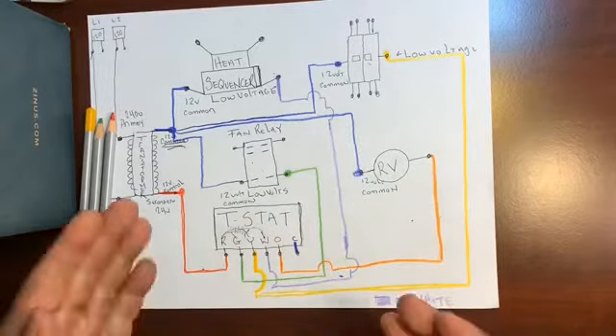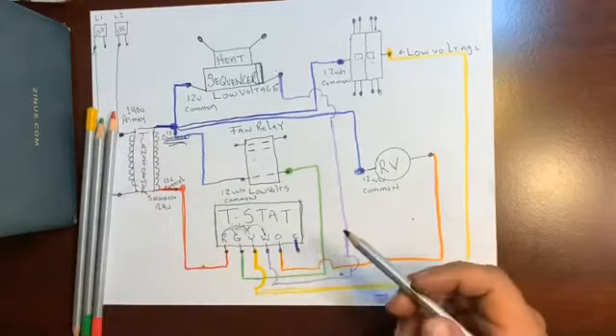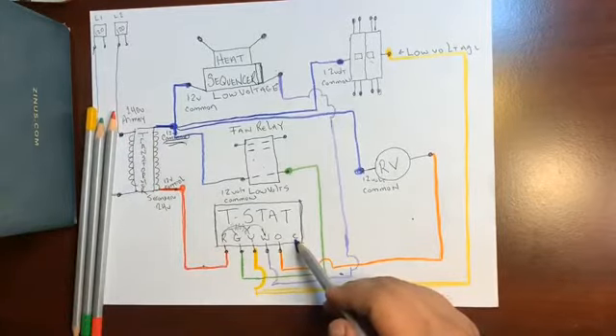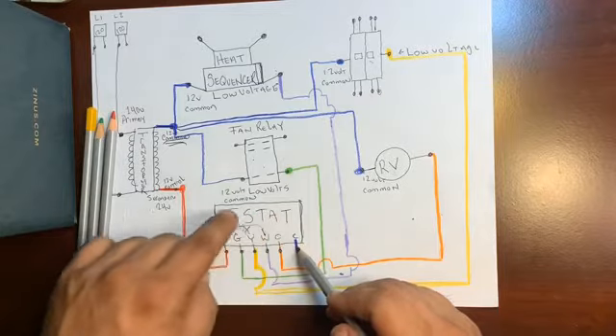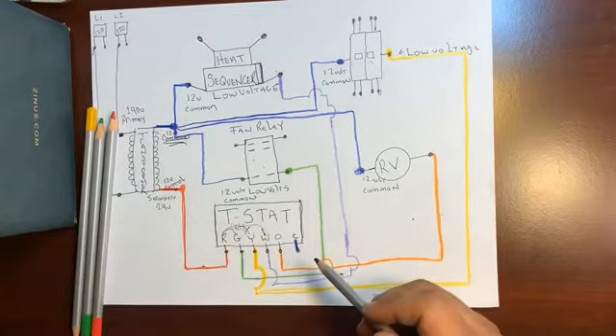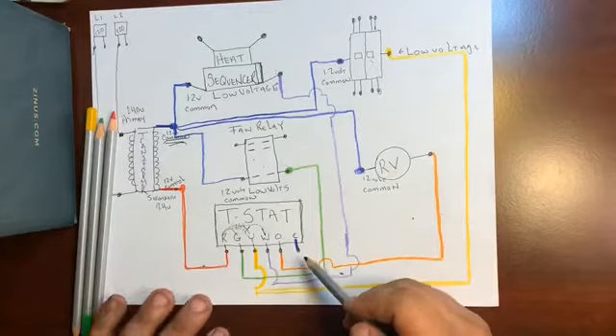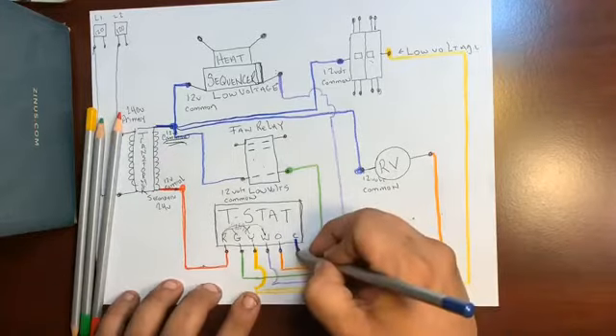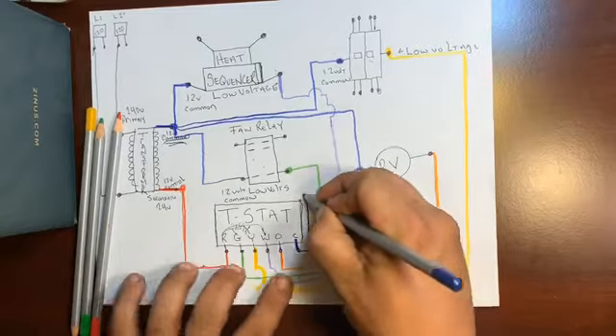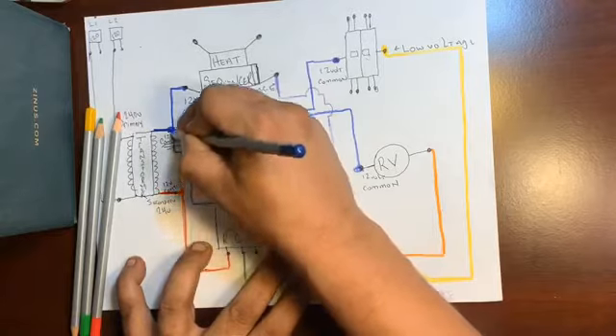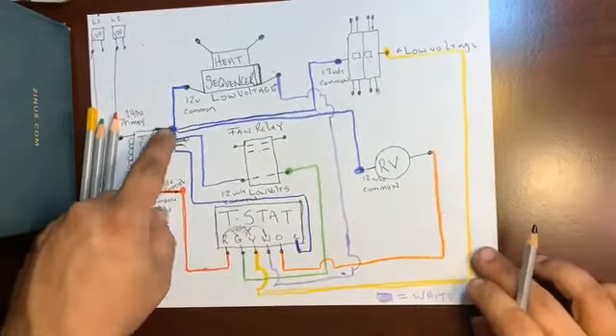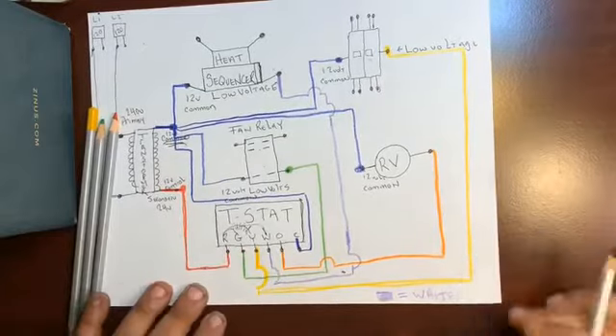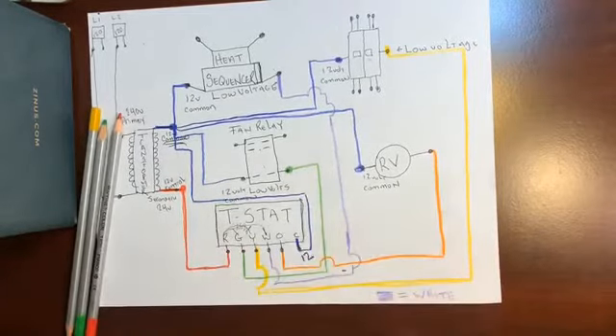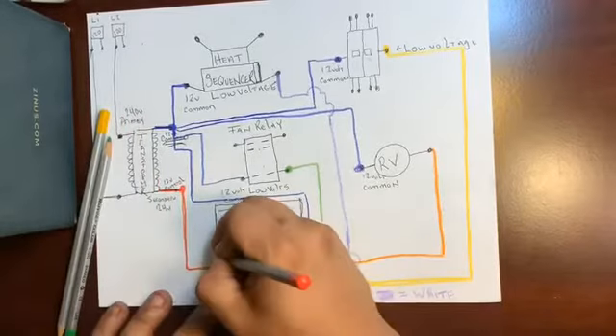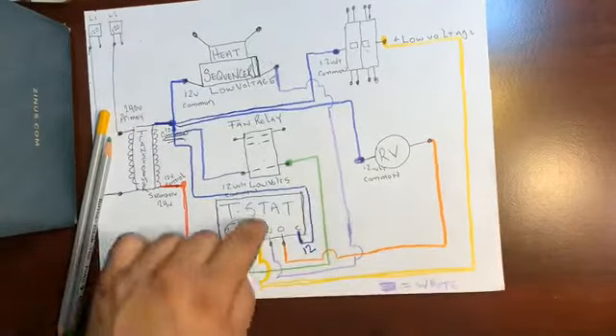The thermostat will get 24 volts from the transformer. If you look at many thermostats, it says C is optional with batteries, meaning if there's batteries in the thermostat, then you don't need a common wire. But the higher end thermostats that have no batteries have to have a common. So how do we do that? There's another common that leaves here, goes back here, and also ties in with common. So your thermostat will get 24 volts. It'll get 12 volts here, and then it would also get its 12 volts on its red side. And that's how our thermostat gets 24 volts.